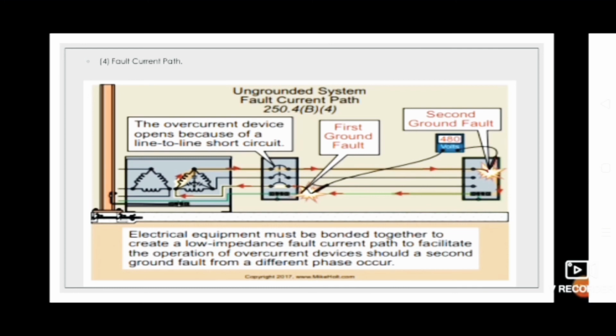Electrical equipment, wiring, and other electrically conductive material likely to become energized must be installed in a manner that creates a low impedance fault current path to facilitate the operation of the overcurrent protection device should a second ground fault from a different phase occur.